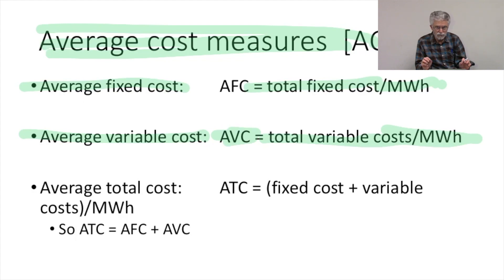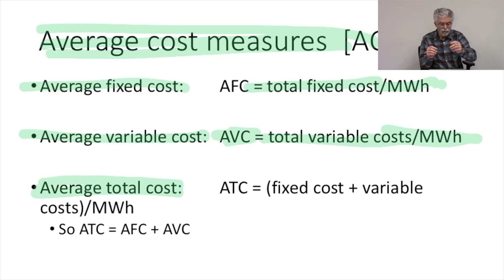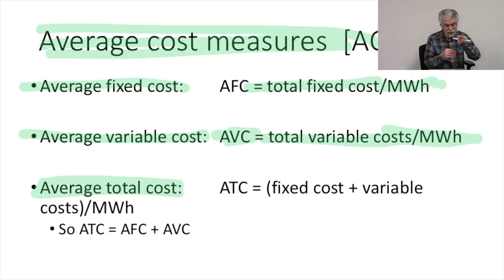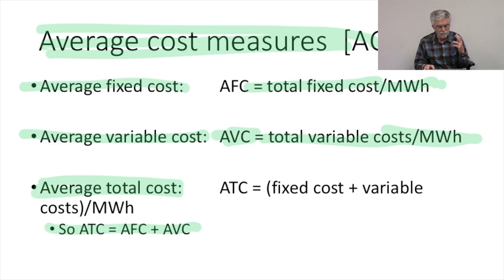What's interesting is that there's a constant relationship between our average total costs, our average fixed costs, and our average variable costs. Our average total costs are just the sum of our average fixed costs and our average variable costs. So for any given capacity factor, we can calculate our average total cost by adding up the average fixed costs — that monthly payment we have to make — plus the payment we make per megawatt hour generated. It's a relationship we'll come back to time and again as we go through our cost calculations.